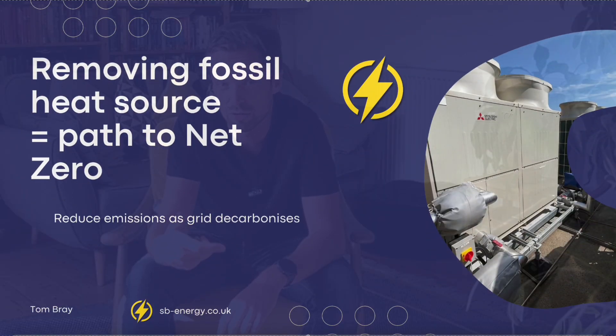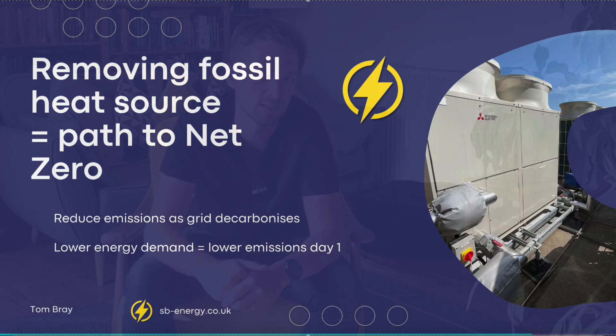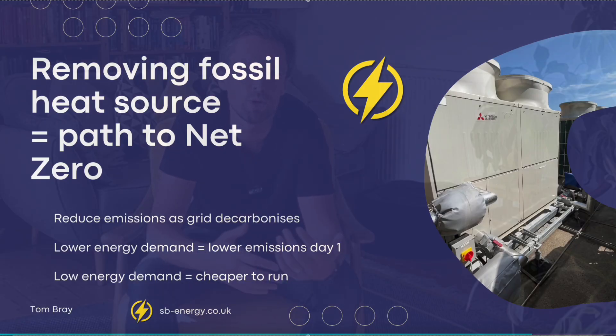Back to Bolden House — I didn't have the data for the building in use before the refurbishment as it had sat empty for several years. But when I compared this building to buildings with similar uses per square meter that I did have data for, it looks like this building uses less than half the energy of buildings with a similar use. This means that the site has a path to net zero and will continue to reduce emissions as the electricity grid decarbonises. The improvement in systems and efficiency also means it uses a lot less energy than similar buildings, making it lower emissions today even with emissions still on the electricity grid. And because it's using that much less energy, it's also cheaper to run than more modern buildings with similar usage.